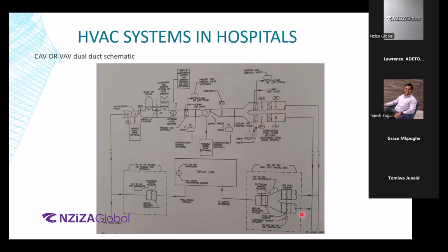Now at a given time, it can happen that both of the systems are on, heating and cooling both. They go into this dual duct VAV box, and then the temperature sensors over here will take care of modulating how much air from both sides needs to be introduced into the zone. Does that make sense? Two ducts coming out and two ducts going into the VAV box. One is the hot air duct, one is the cold air duct. Yes, you had a question?